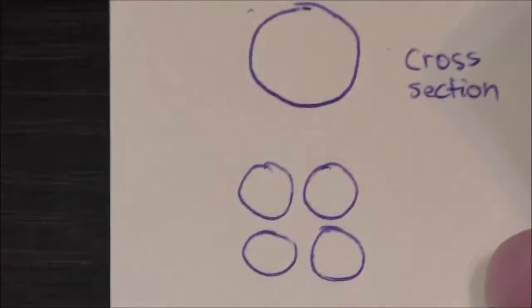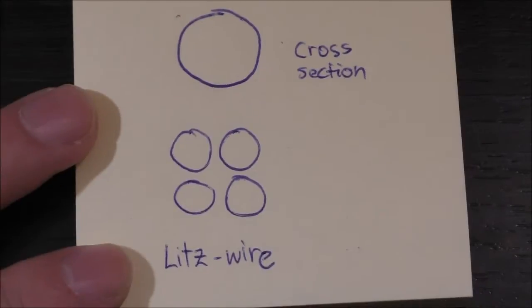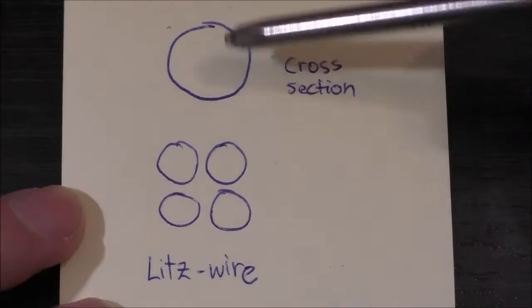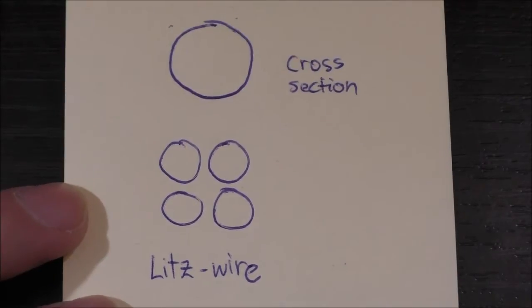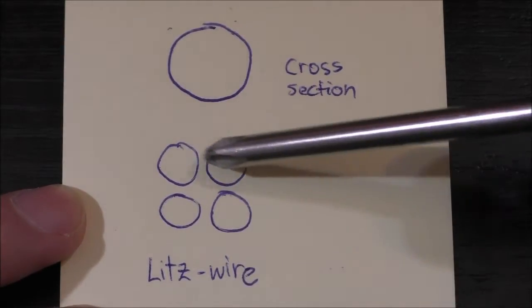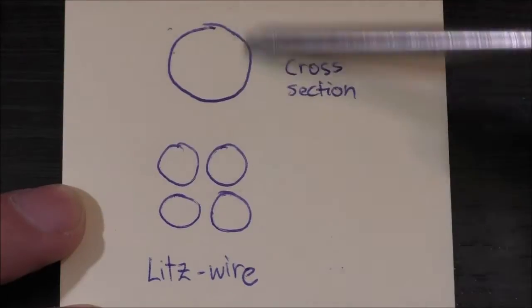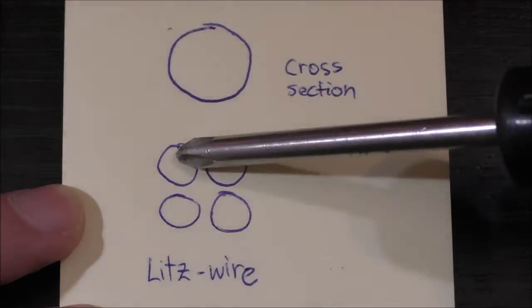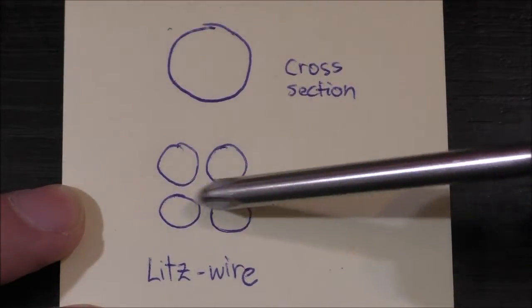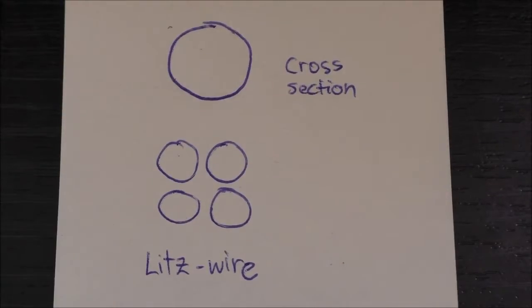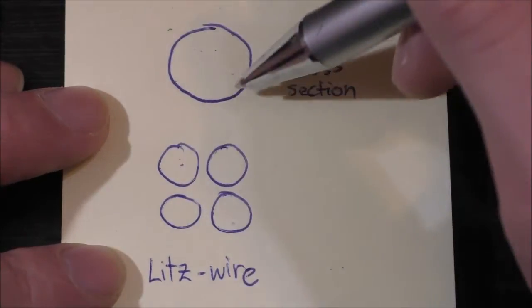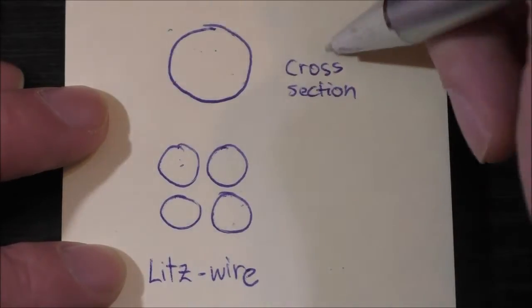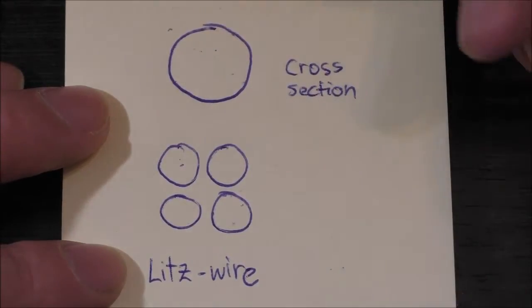So over here we have the cross section of a standard conductor. And in the litz wire construction, we actually made this larger conductor out of smaller, thinner diameter conductors. Now the total cross sectional area of these two wire bundles might be the same. So the total cost of copper would be the same. However, if we look at the surface, the outer surface area of the conductor...